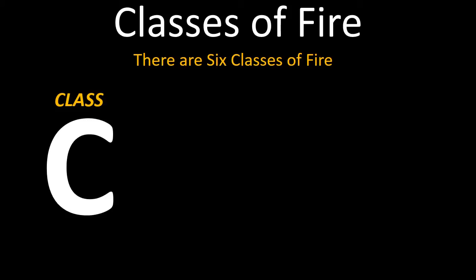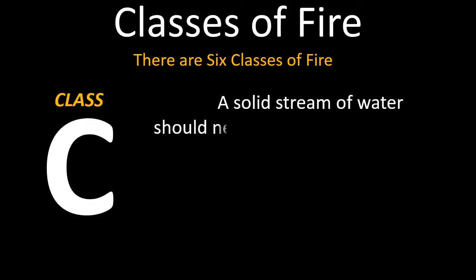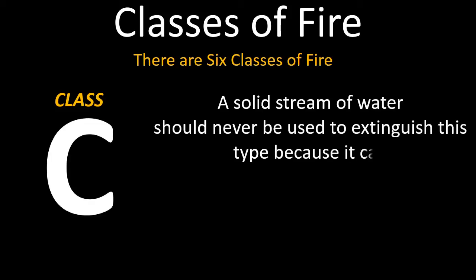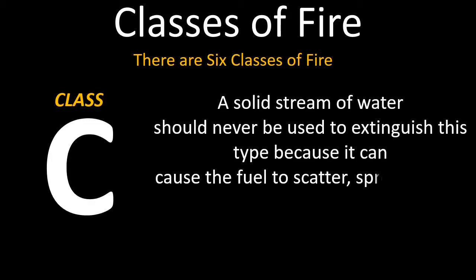Class C fire is just like an ordinary combustible fire except that the fuel used is a gas, such as natural gas. A solid stream of water should never be used to extinguish this type of fire because it can cause the fuel to scatter, spreading the flames further. The most effective way to extinguish a liquid or gas fuel fire is by inhibiting the chemical chain reaction of the fire, which is done by dry chemical and halon extinguishing agents.